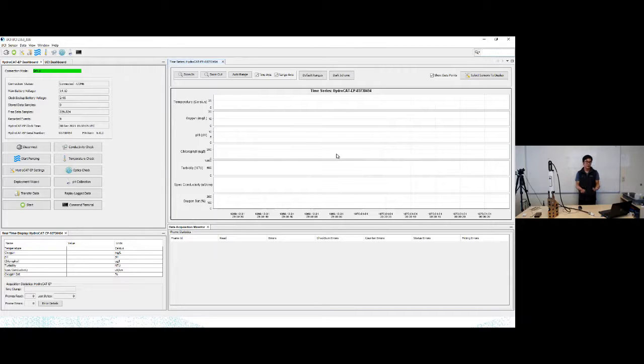It's a good way to just visually check your data, see if things are within range, see if the amount of data you have in here is expected. Word of warning, if you have thousands upon thousands of samples in your instrument's memory, it can take a while to actually populate these data. So keep that in mind if you're in a rush.